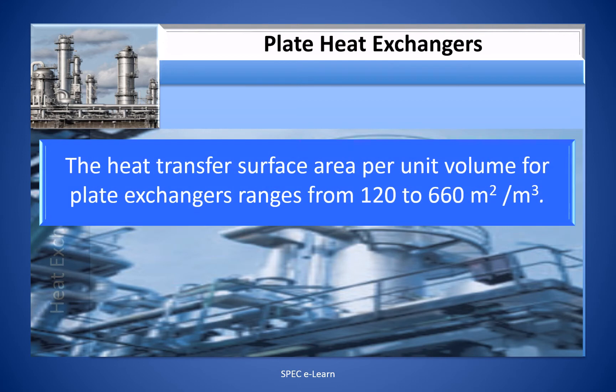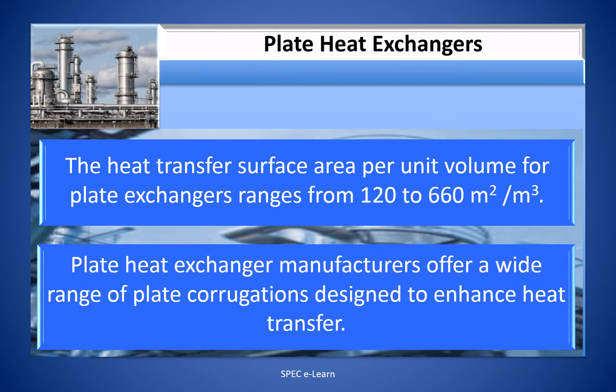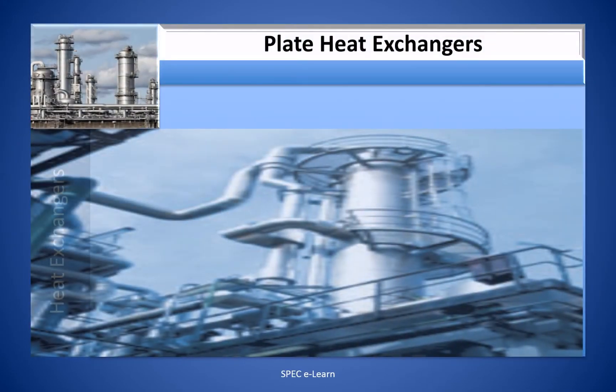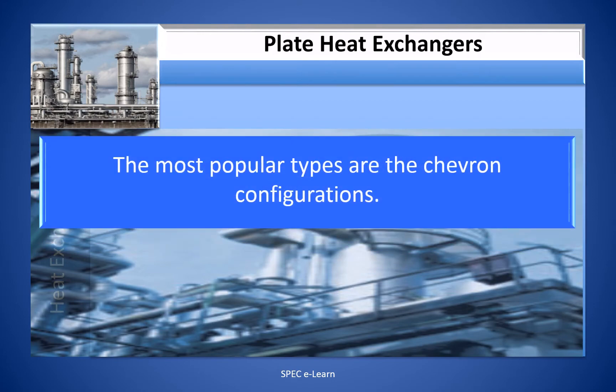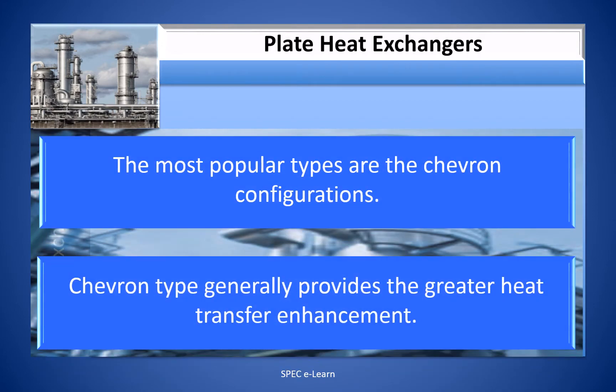The heat transfer surface area per unit volume for plate heat exchangers ranges from 120 to 660 m² per m³. Plate heat exchanger manufacturers offer a wide range of plate corrugations designed to enhance heat transfer. The most popular types are the chevron configurations, which generally provide the greatest heat transfer enhancement.